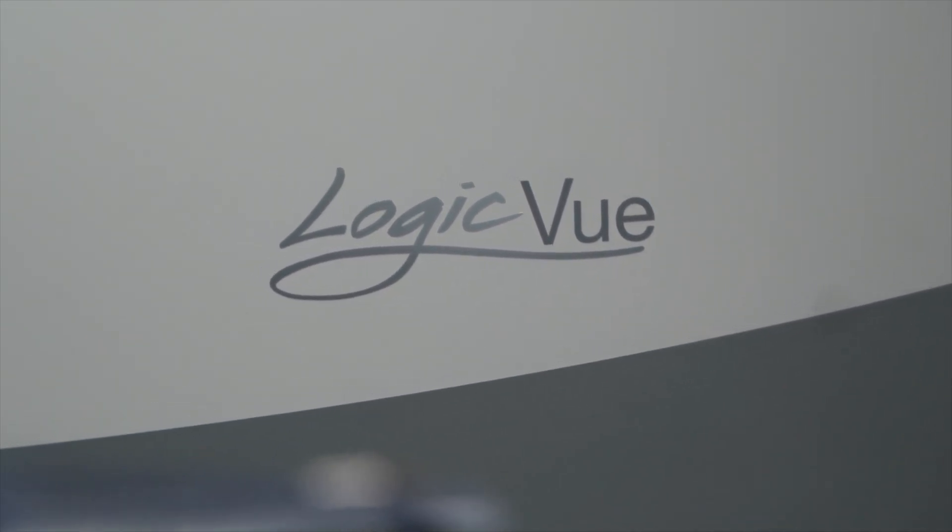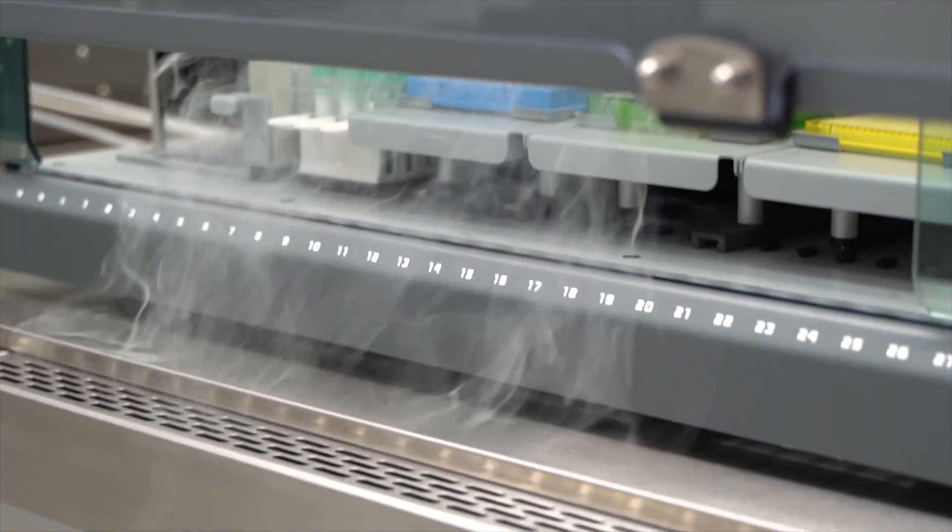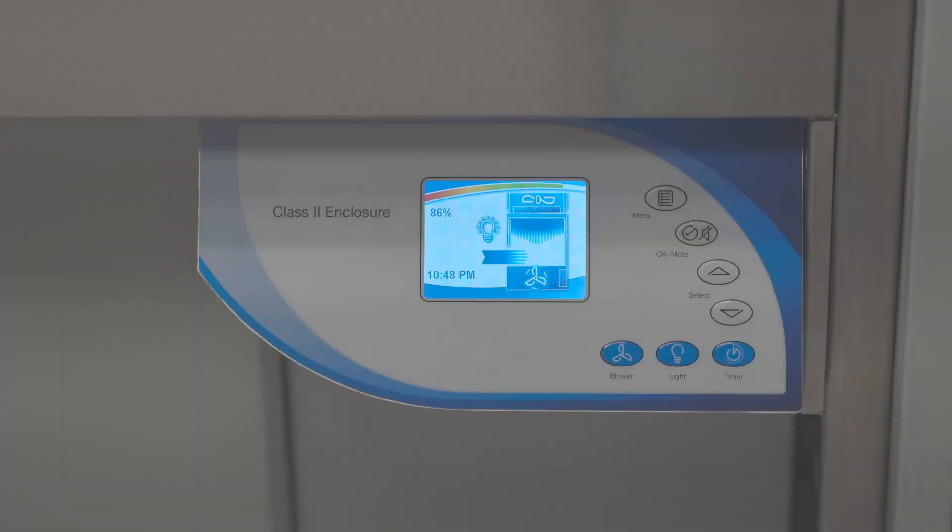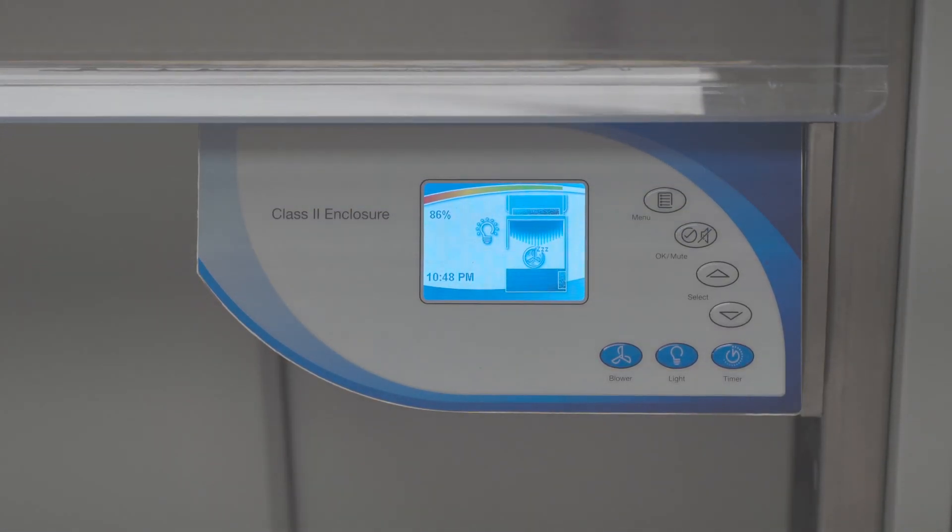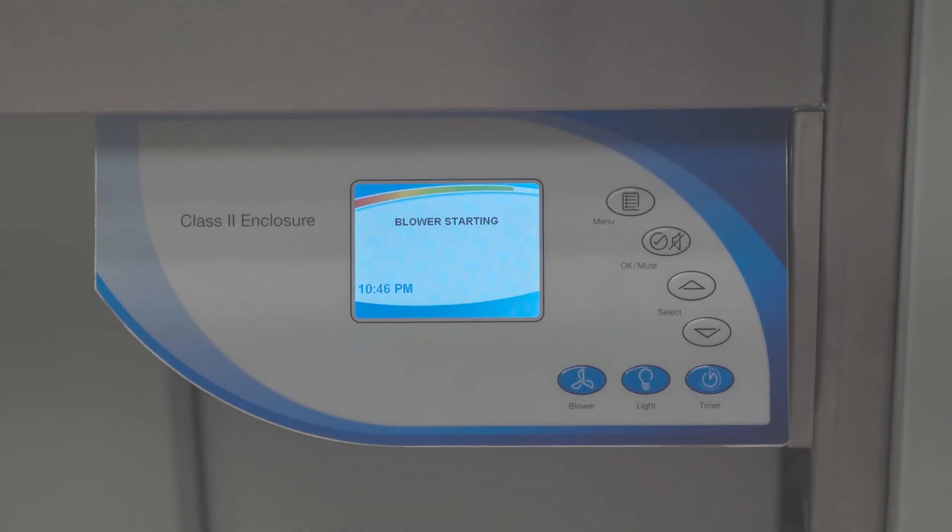Safety is at the core of the LogicVue, exceeding NSF 49 requirements for Class II personnel and product protection. HEPA filters trap 99.99% or more of particulates 0.3 microns in size, and LabConco's constant airflow profile technology monitors and maintains safe airflow at all times.